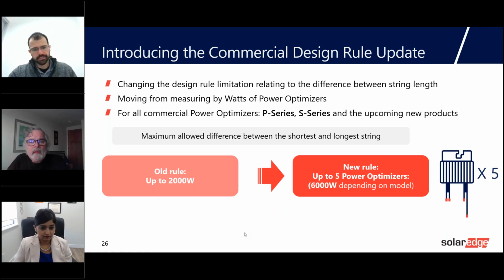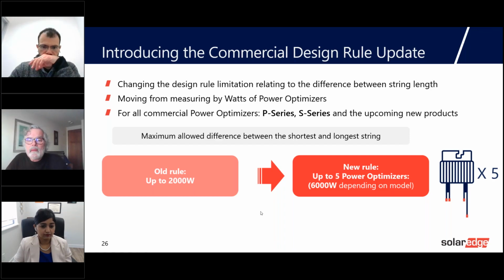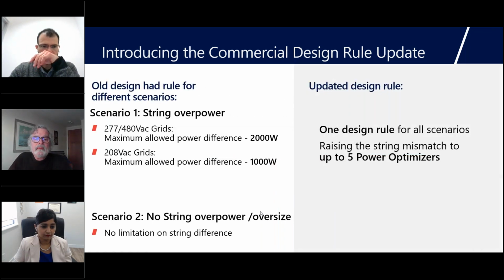So instead of having a 2000 watt delta, we now just allow you to use five optimizers per string, which makes it a bit simpler to calculate. It also supports a much larger delta in terms of power, depending on the size of the PV modules you're using. So it could be up to 6 kilowatts per string of delta, depending on how large the modules are. And next slide, please.